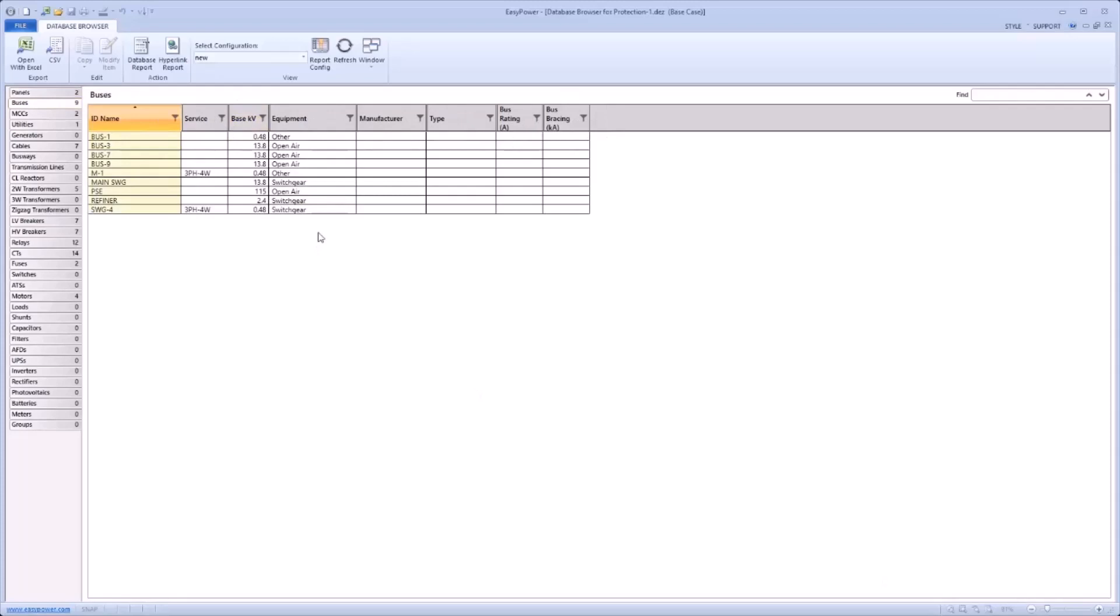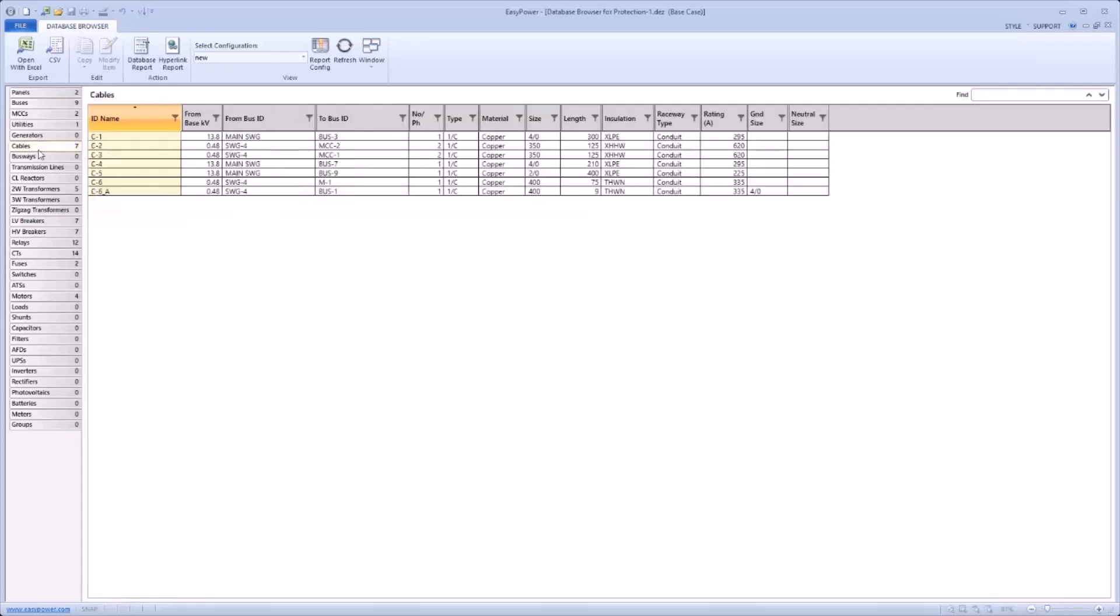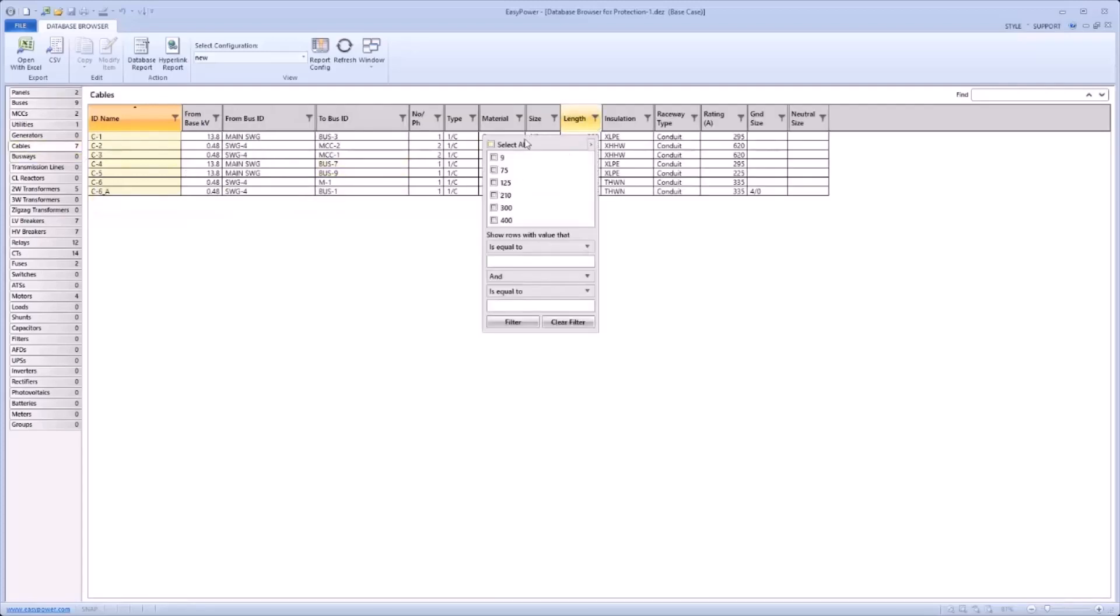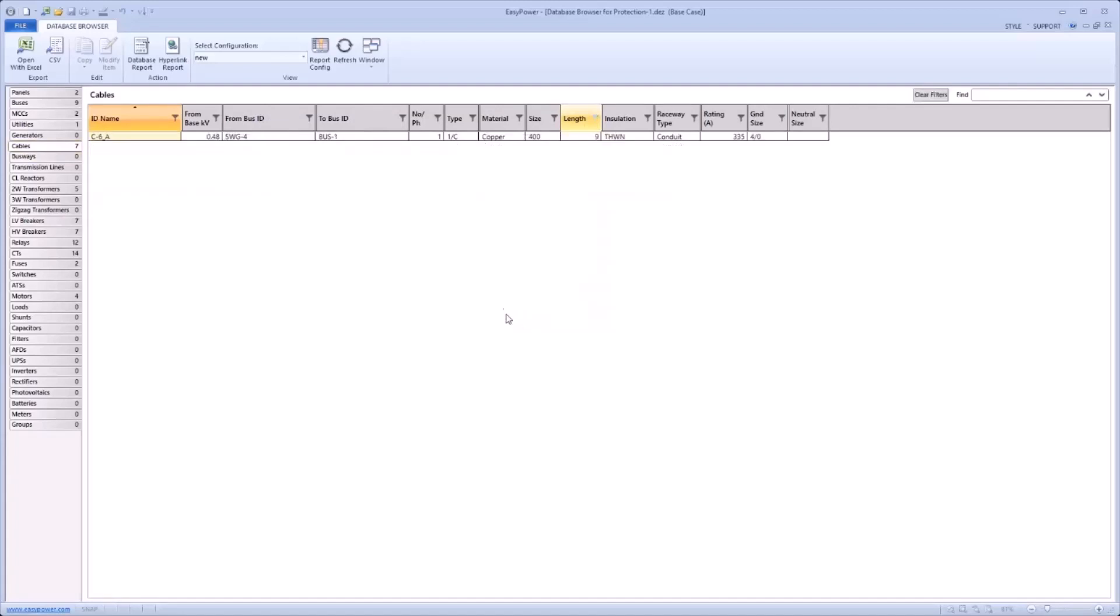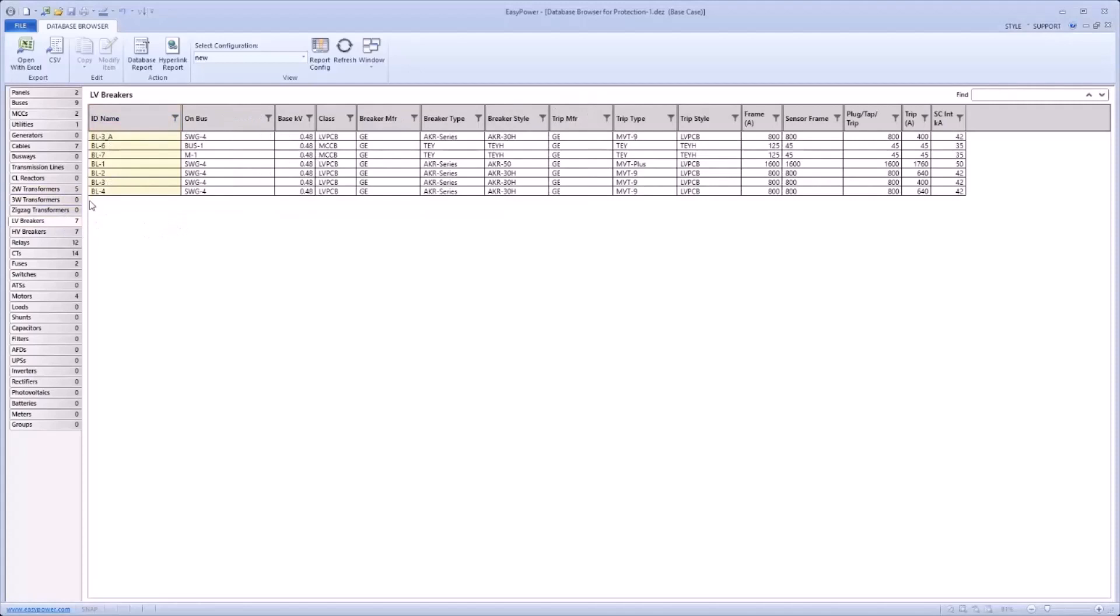In addition to the report configuration enhancements, there is now support for both sorting and filtering data columns. For example, one could navigate to cables and filter for an assumed length, in this case maybe nine feet, filter, and as can be shown, only nine foot cables are shown. Or, moving to low voltage breakers, one could sort by the on bus column to allow for easy grouping of breakers for use in the field.